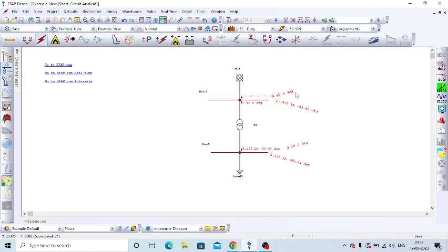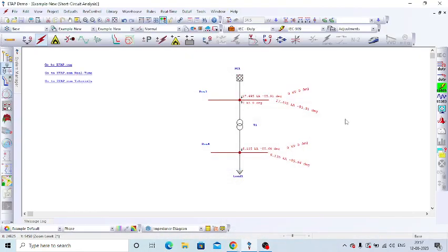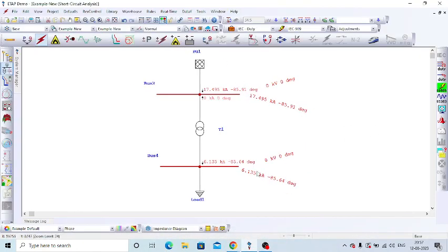Okay, so I will tell you how to see that result. Here we are getting multiple values. So the first one is the voltage. So presently this bus 3 voltage at the time of fault is 0 kV and voltage angle is 0. For the bus 4 also, the voltage is 0 kV and voltage angle also 0. So it means it is a 0 voltage fault. So it is zero impedance fault. So normally we will call it a bolted fault.